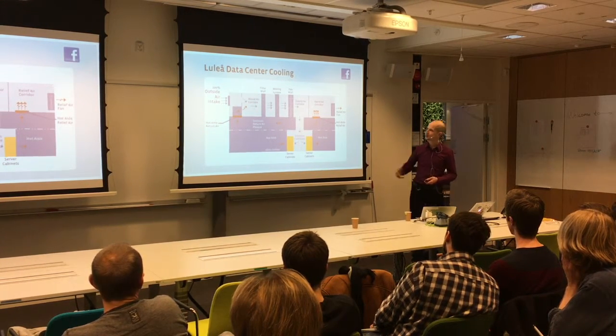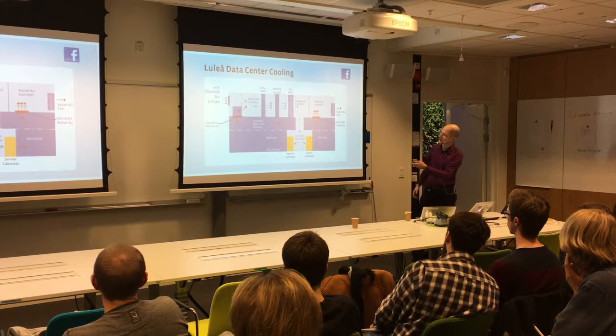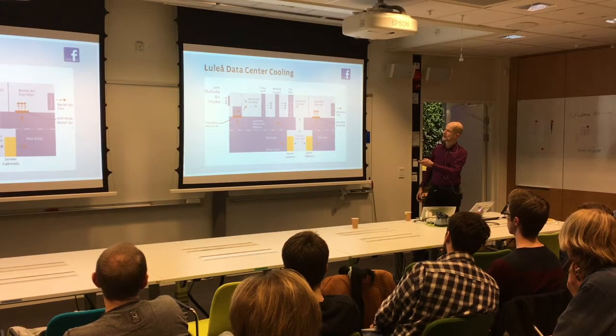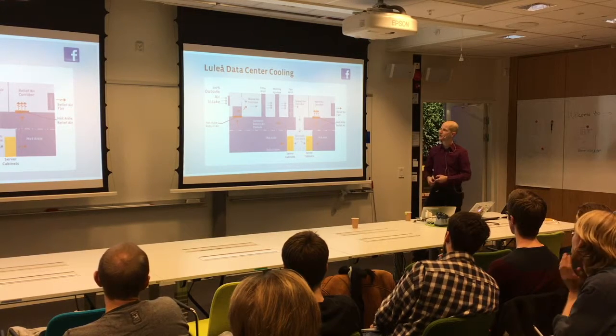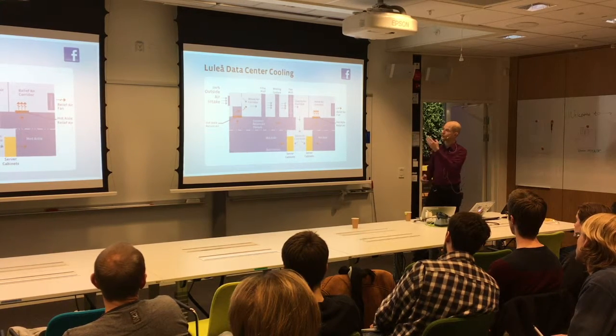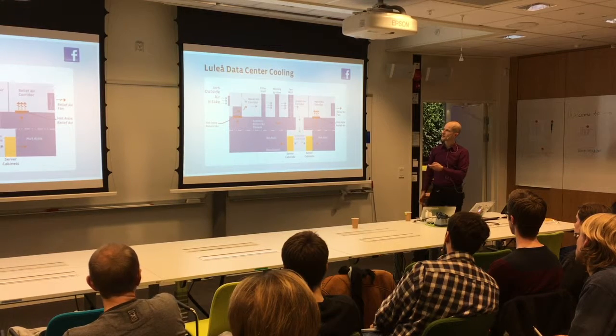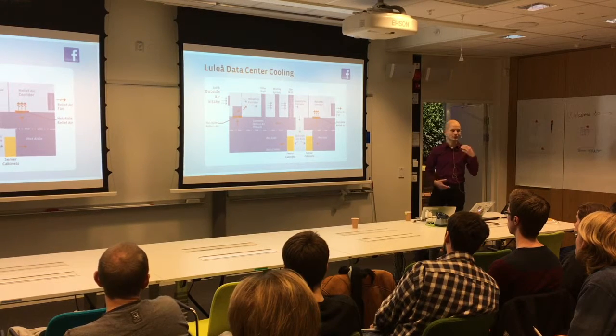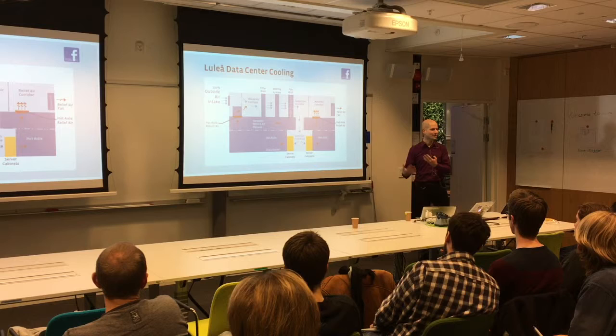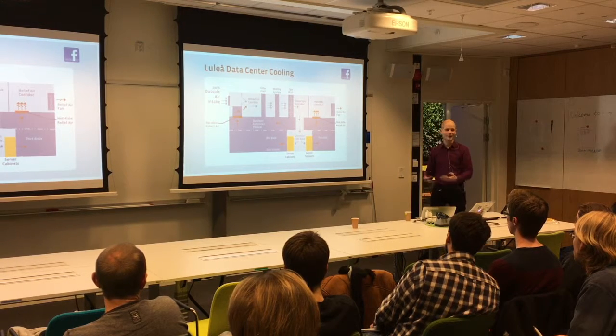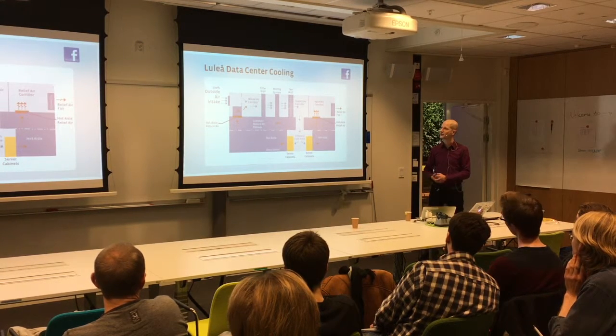So what we do is take in outside air that we mix with hot return air from the data halls to get the right temperature without building up too much pressure. We pass that through a series of filters to get rid of dust, pollen, insects, and anything else you don't want inside the data center—once it gets in, you can't get it out, and it decreases efficiency.